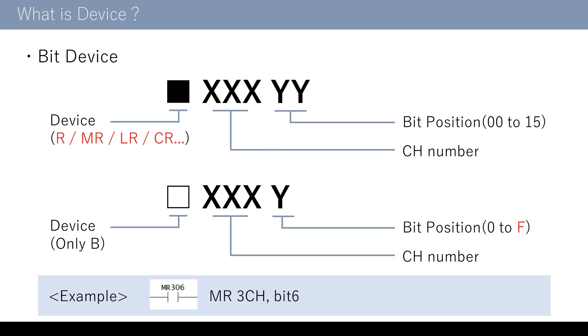I will explain about the device notation. The first one is a bit device. Bit devices are displayed with the device name and the device number. There are several device names. R is the device which the unit function is allocated. MR is the internal auxiliary relay which turns on-off only in the program. LR is the device which memorizes the on information even when the power is off. CR is the device which the PLC system information is allocated. In the device number, the last two digits indicate the bit position, and other digits indicate the channel number.